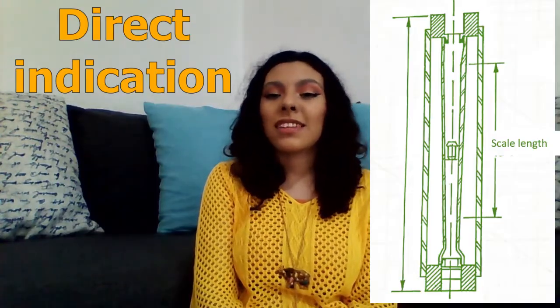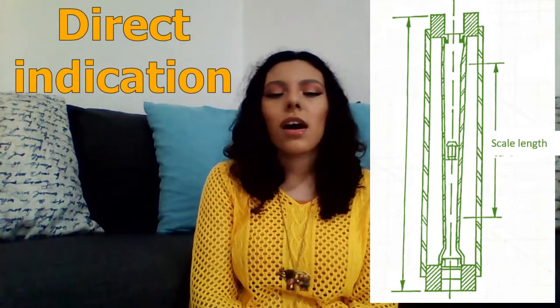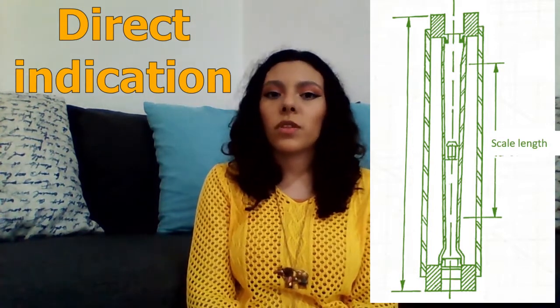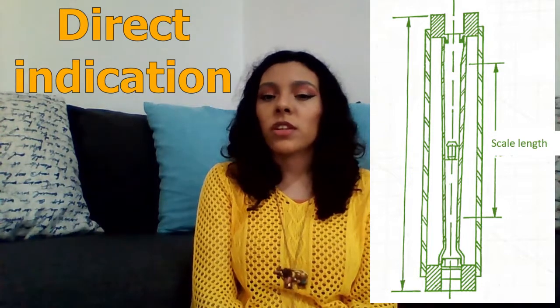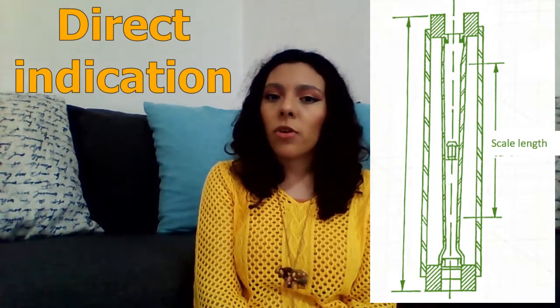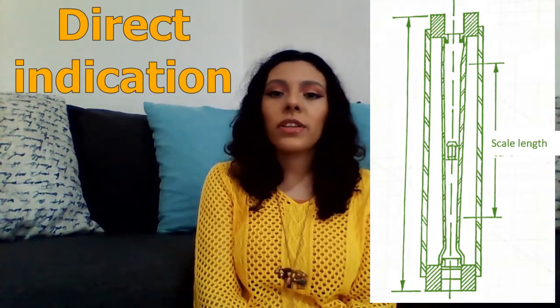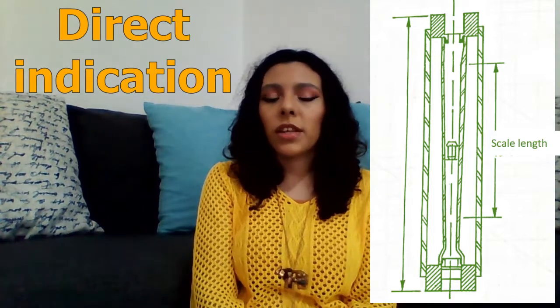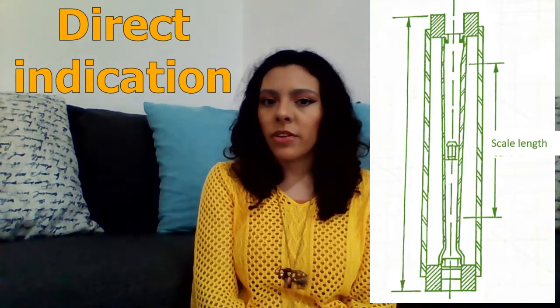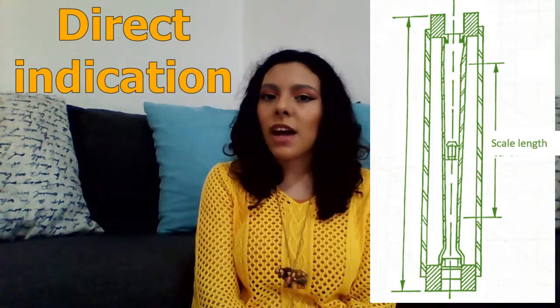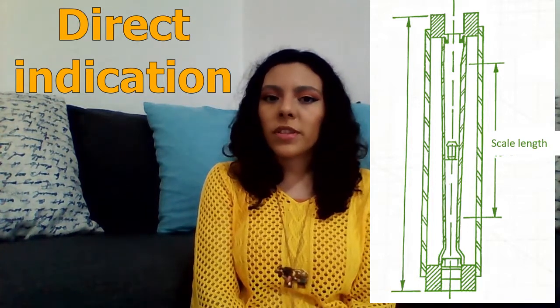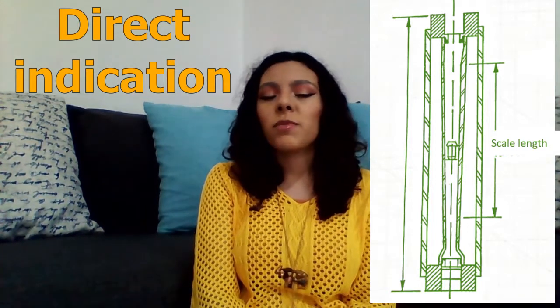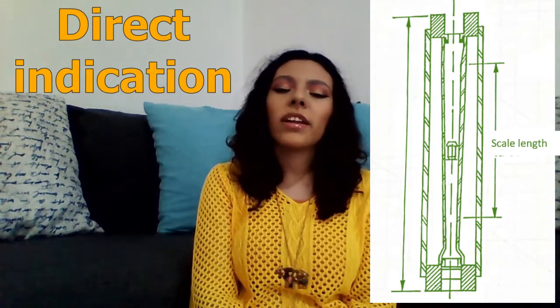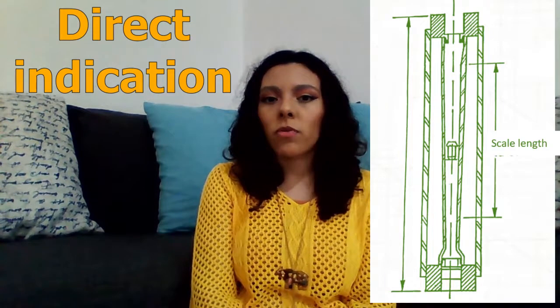Direct indication glass rotameters can have side plates, be closed with 4 plates with a glass window to see the tube, have a security armor of watertight closure to avoid that in case of the tube breakage, the inner fluid can damage the operator. It can also have an anti-freeze armor with silica gel to avoid the presence of humidity in the space between the armor and the tube, so that it doesn't impede the visibility of the float.